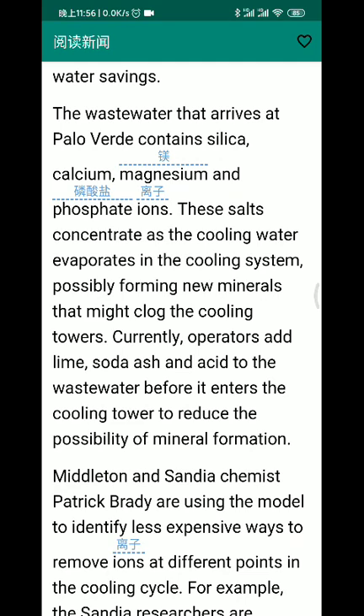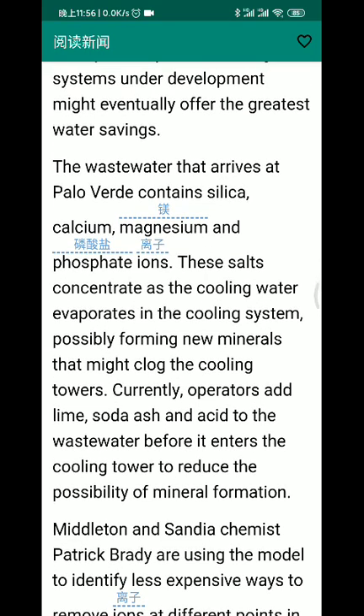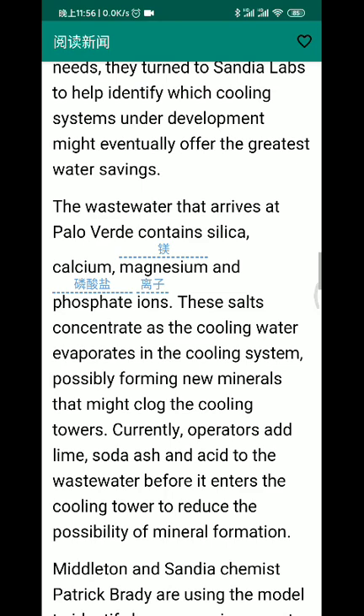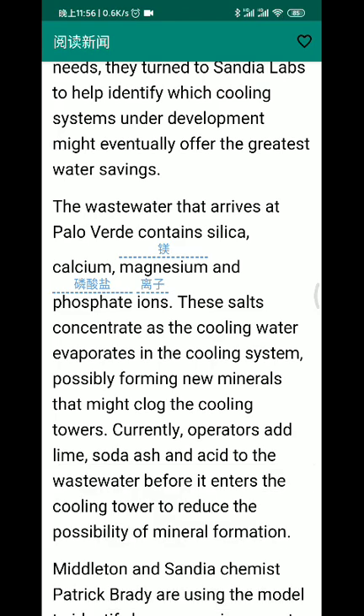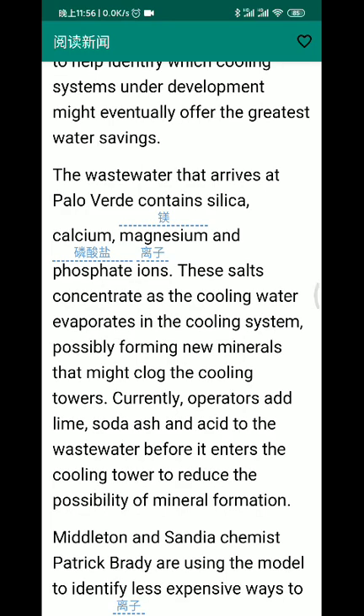The wastewater that arrives at Palo Verde contains silica, calcium, magnesium, and phosphate ions. These salts concentrate as the cooling water evaporates in the cooling system, possibly forming new minerals that might clog the cooling towers.